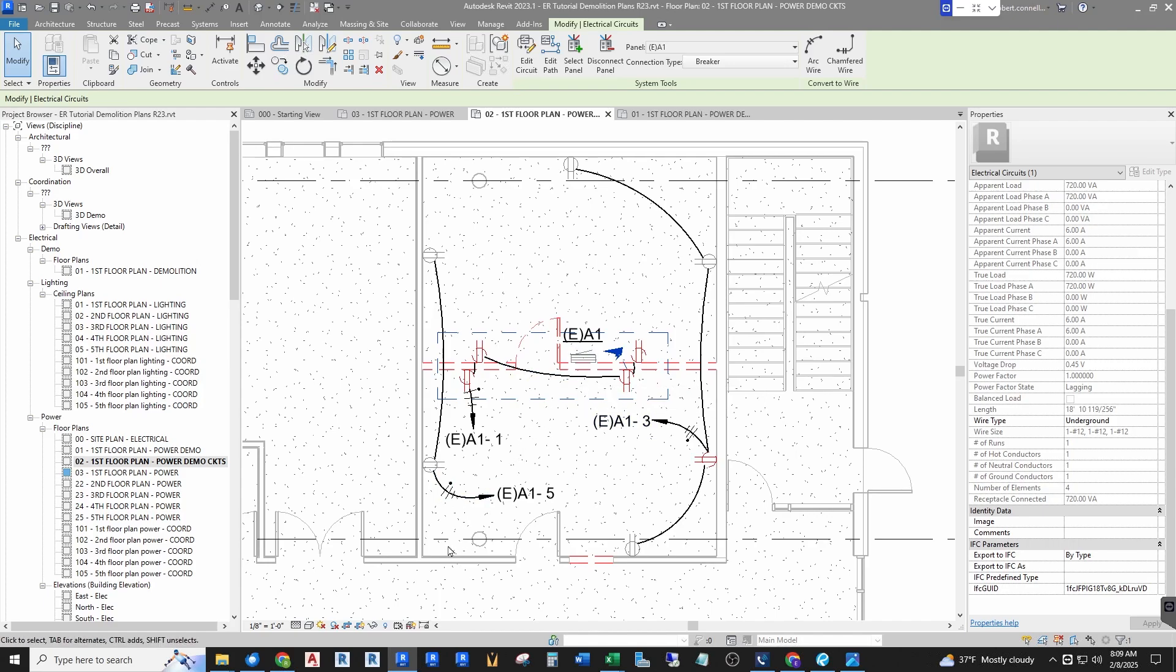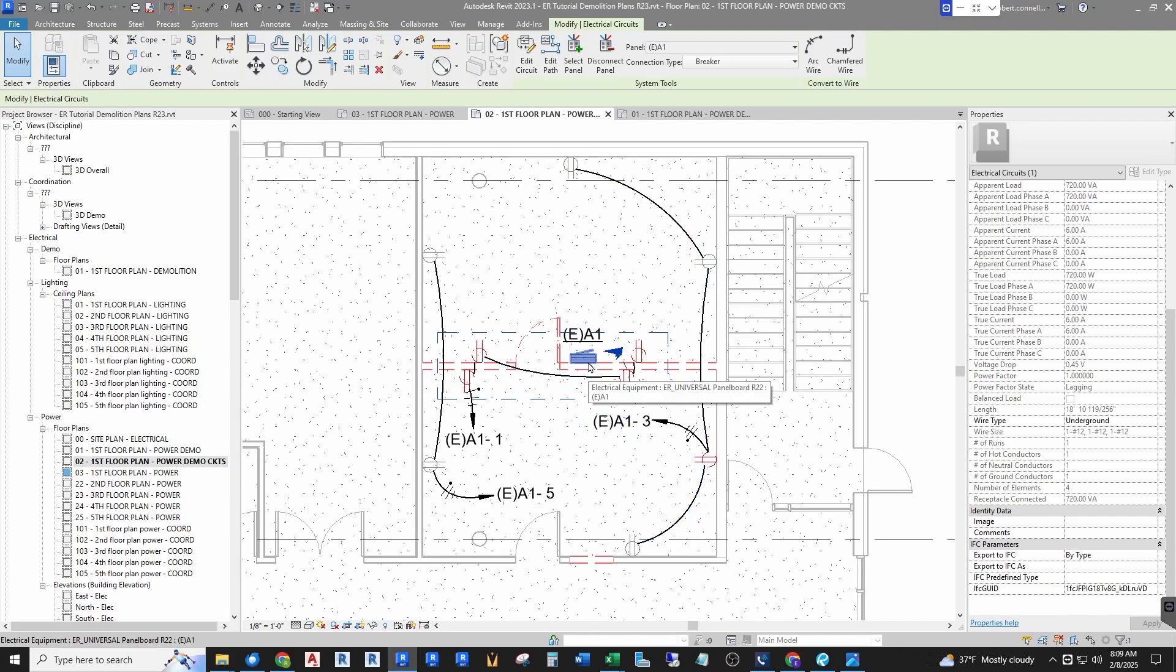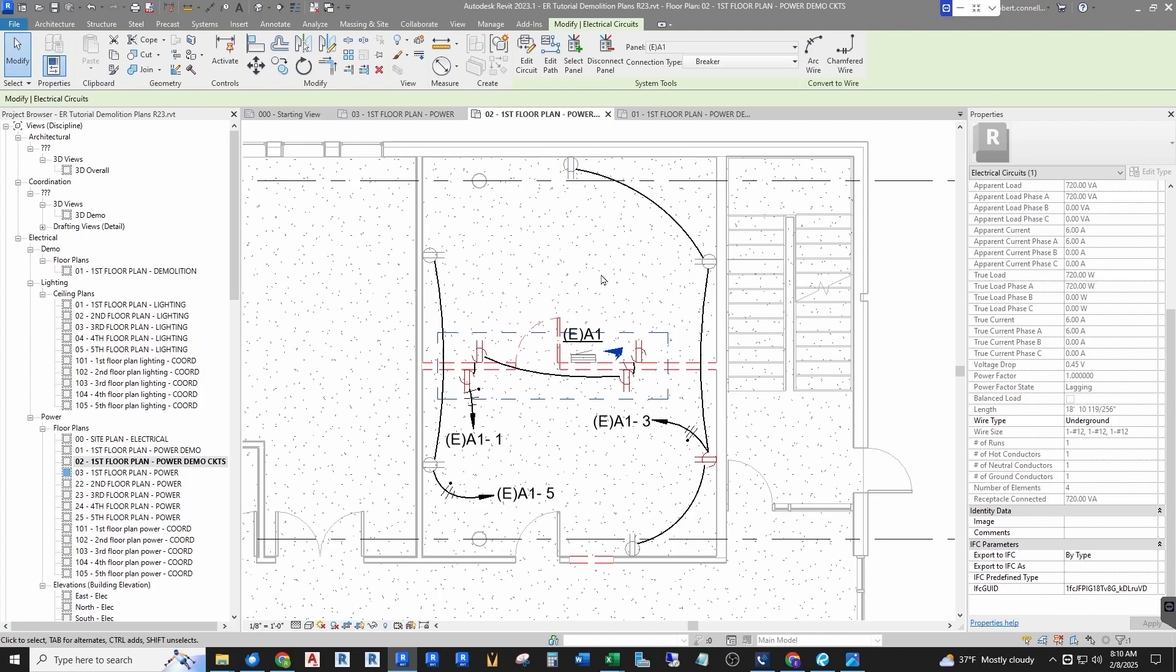So that we cannot have demoed circuits and new circuits, can't have both. I'm currently working with a client who does a lot of renovations, remodels, and this happens a lot. We have a lot of panels that are being removed from a wall that's coming down and moved to a new location or a new panel put up, things like that. So we've come up with this kind of a workaround. We would not show these red ones being circuited and we would not show these existing being circuited to a demo panel. We would instead just put some kind of notes for the demo plan about these existing circuits being demoed. That's even if you know the circuiting, if you have existing as-builts or record drawings or in the field if you can tell, we would do that with notes. We'd like to have two panel schedules, an existing demo panel and a new panel.